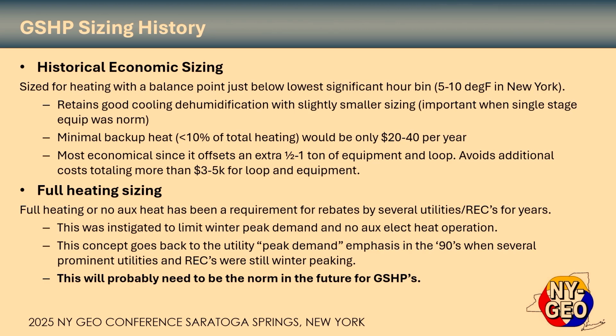Now, switching over to the ground source heat pump, historical sizing for ground source heat pumps: when I first got in the business, we were trying to limit first cost. So you typically would size the heating for a balance point really just below the significant bins of a lot of hours, right? Because you're going to limit the size of the equipment to a certain extent, maybe trim a ton off the equipment, a ton off the loop, and your first costs are lower. So you can still retain good cooling dehumidification with a slightly smaller unit, and back when we were selling single speed equipment a lot, that was important, and so that all made sense back then.